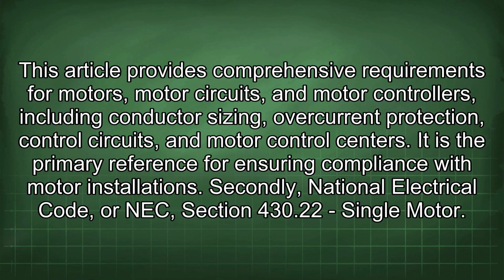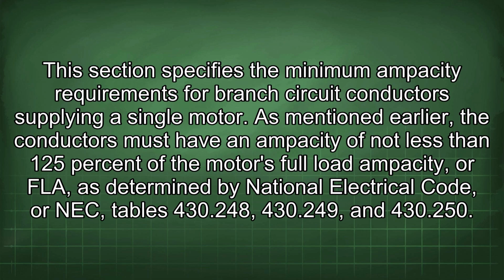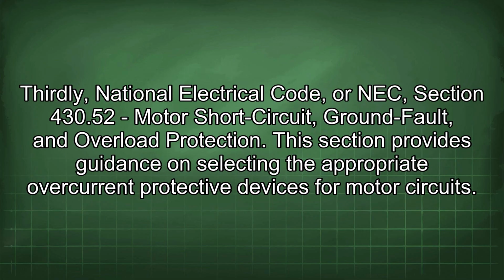Secondly, NEC Section 430.22 Single Motor. This section specifies the minimum ampacity requirements for branch circuit conductors supplying a single motor. As mentioned earlier, the conductors must have an ampacity of not less than 125% of the motor's full load ampacity, or FLA, as determined by NEC Tables 430.248, 430.249, and 430.250.